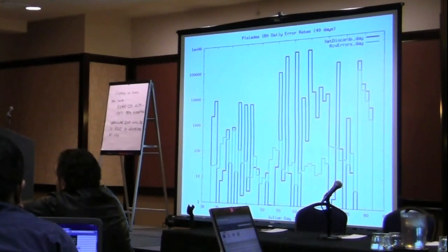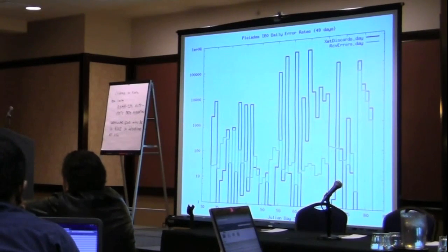In this ICE system, it's actually through a backplane connector, and those connections are much more reliable than the cables. So we typically don't see problems there. And if we do see a problem, it's typically a problem in the HCA, although sometimes we'll have interface or mechanical issues on those connectors that'll cause problems. But I just wanted to isolate that part out.